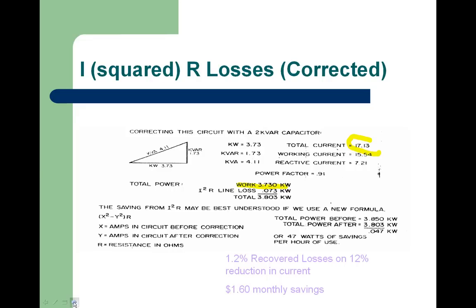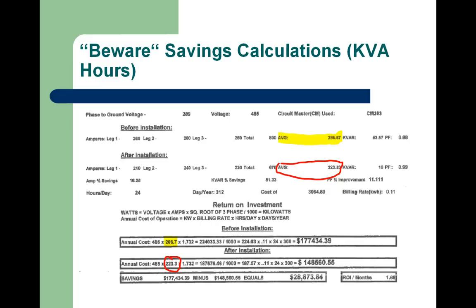In any case, we're on to the next slide. I have a little "beware" up here. This was something that a customer had sent to me, from a company that had been selling a capacitor bank, and this would be distributed throughout the facility, much like we had on the previous slide. In this particular one, this is measured in amps, as before. We have an average of 266 amps with a power factor of 88%. They put in some capacitors, and the current dropped down to 223 amps with a power factor of 99%, which one would expect to happen.